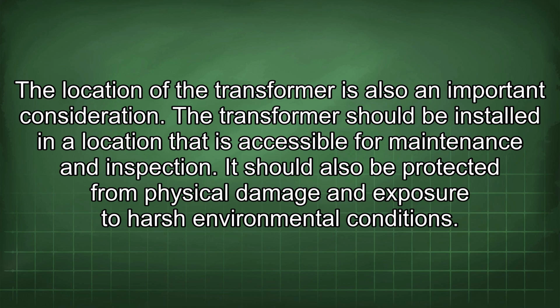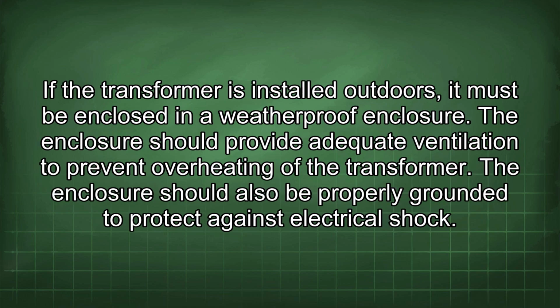The transformer should be installed in a location that is accessible for maintenance and inspection. It should also be protected from physical damage and exposure to harsh environmental conditions. If the transformer is installed outdoors, it must be enclosed in a weatherproof enclosure. The enclosure should provide adequate ventilation to prevent overheating of the transformer. The enclosure should also be properly grounded to protect against electrical shock.